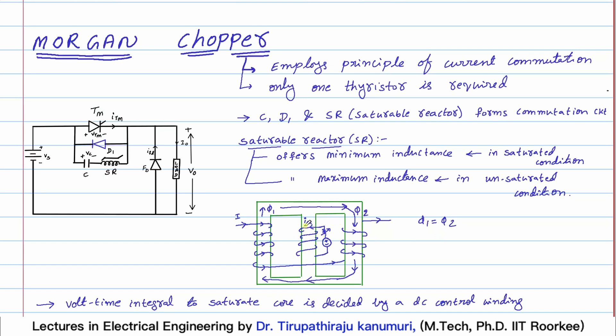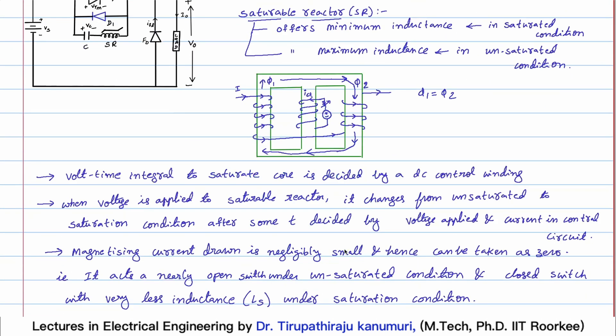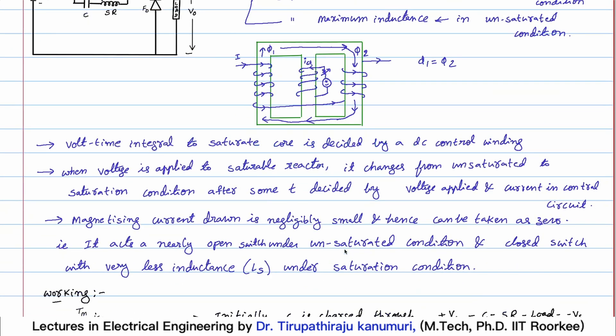Because the net flux in the central limb is zero, the flux produced by these two windings is not linking with the central limb winding, so no EMF will be induced - it will not affect any control circuitry. This basically involves a DC source with some control resistor that can be adjusted to pass current through this winding, controlling the amount of flux existing in the core and thereby driving the device into deep saturation.